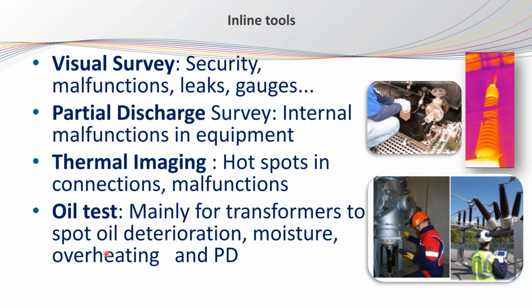So if we speak about the inline tools very quickly, the most famous inline tools when it comes to power transformers: visual inspection, the easiest one; we have the partial discharge, and we can do simple routine PD surveys. There are a number of equipment that can be used to do the PD surveys. The simplest one is something like this here, and it's just an instrument that can detect PD based on radio frequency interference. And we have thermal imaging to detect any hotspot, and of course the routine oil sampling that we are all doing from time to time from the power transformers.